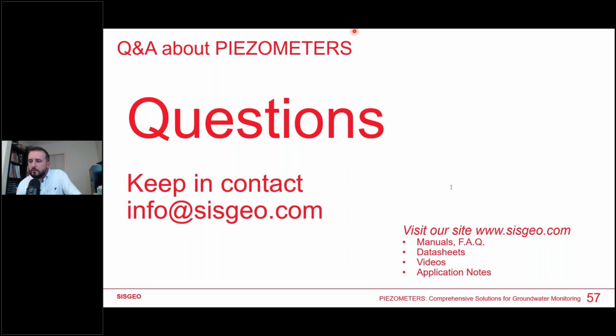Can we use vibrating wire pressure in open standpipe both? Yes, you can use vibrating wire pressure. The technology of vibrating wire or strain gauge is just the output signal. So the output signal has no influence on the use that you will make of it. So you can use the vibrating wire pressure transducer for a standpipe, but you need to have a barometric compensation, because the vibrating wire sensor cannot be relative.